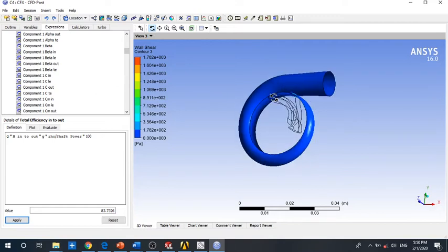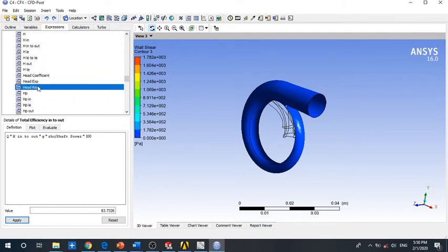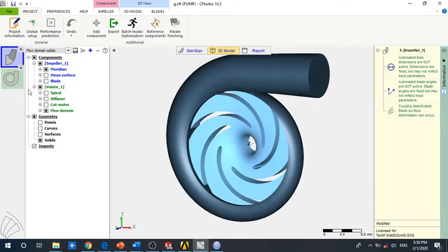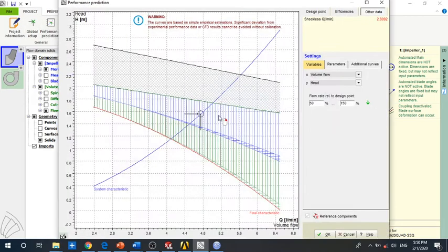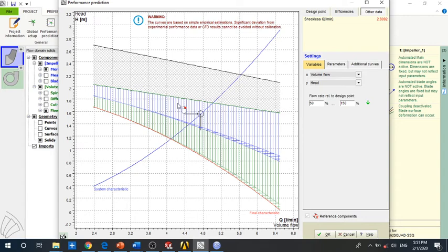And by the way, a very important piece of advice here, if you go to the head, we go back to the head rise. Okay, you can see here is about 2.17 meter. Okay, but as you go to CF turbo, you have also a performance prediction chart, which is the HQ curve, but here it is drawn by empirical equation rather than a CFD simulation. Okay, so if you go to CF turbo, add a flow rate of about 5 liter, you will get a head of about 1.56 meter.